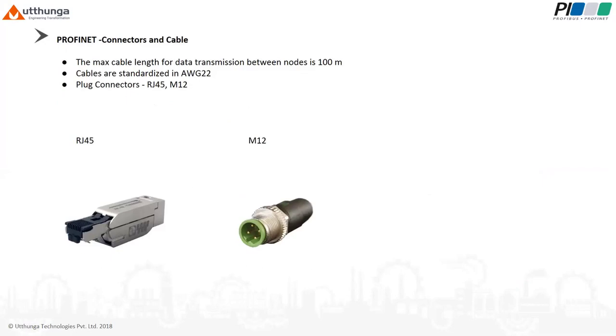Standard cables are AWG-22 and in the Cat5 standard, and the maximum length that can be assured is 100 meters. For connectors, we usually use RJ45 connectors and M12 connectors. And as I said, PROFINET is a 4-wire transmission. There is a color code for each wire. Yellow and orange are used for transmission, while blue and white are used for receiving.